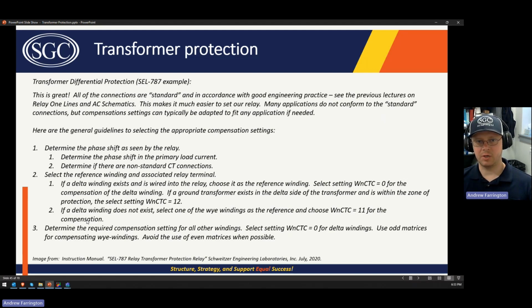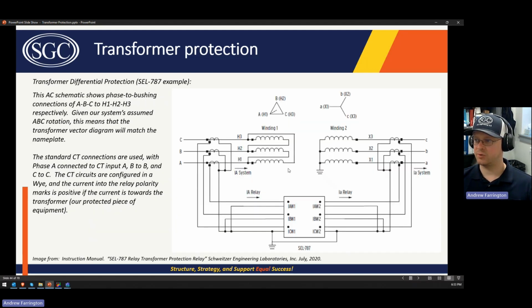And the reason you use 11 and not, say this transformer was a Y winding with a grounded neutral, just like this one, they don't want you to use 12 and 12, which would be what I would intuit, you know, there's no phase shift, so we'll just select them both here, and then we'll remove the zero sequence. Although if it was Y grounded on both sides, you wouldn't actually need to do that because it would be seen by both CTs. But, you know, it might make sense to make them both 12.